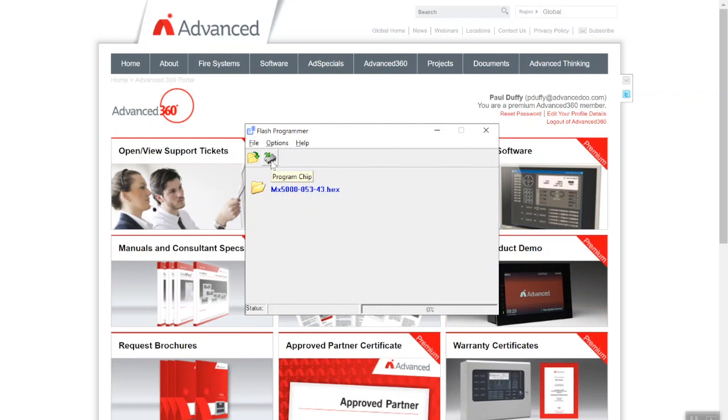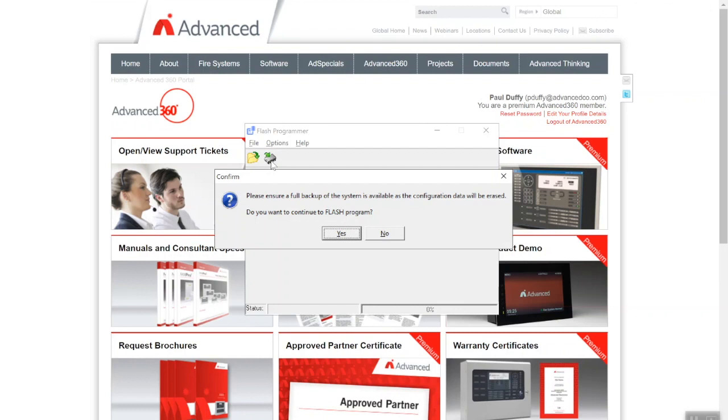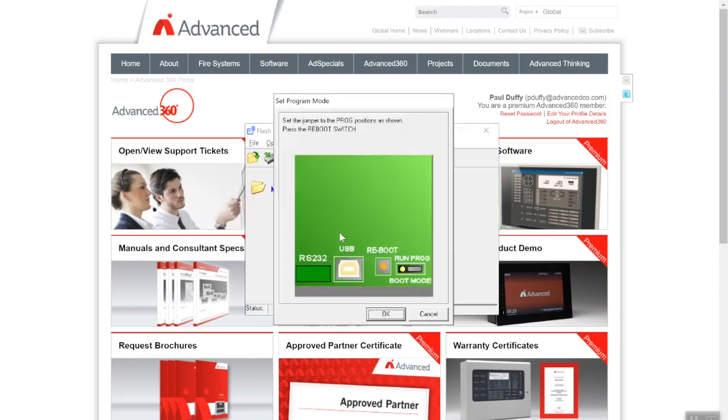Now, pretty important: you see this little chip icon "Program the Firmware." We click the chip icon and there's a warning: Do you want to confirm? Please ensure a full backup of the system is available as all data will be erased. Once we complete this process it will put the panel back to factory default as if it's a brand new control panel. So as good practice you'll have a backup of the software in your office, so backup of the site. It's telling you now just take a backup if you haven't done so already. Do you want to continue the flash program? Yes.